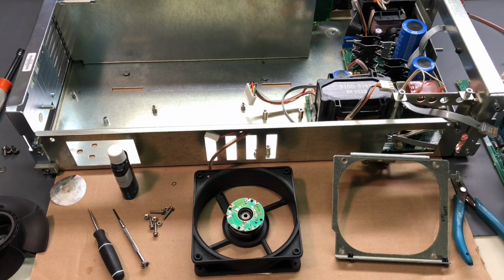So I powered up the fan motor, and it's to be expected. It was starting to get a little bit noisy. The bearings are starting to get dry. That's typical on an instrument like this. It's seen quite a bit of use.